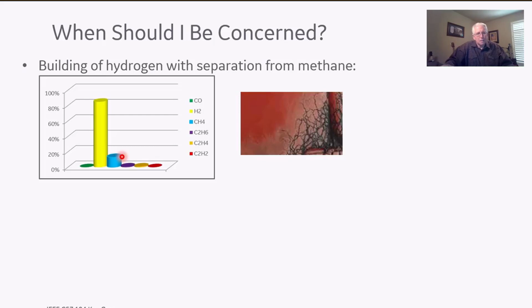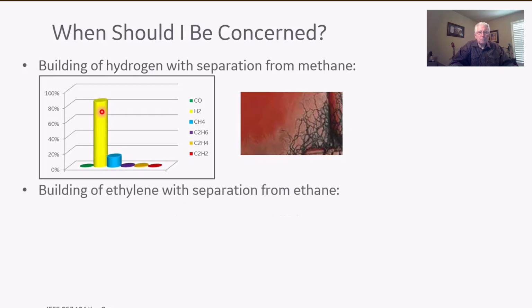the transformer or whatever. But bottom line is, if you begin to generate hydrogen in volume and you're capturing it, and you don't see a lot of movement out of these other gases, you can pretty much take it to the bank. You've got some PD going on in that transformer. So you just need a good separation of relationship here, because they both generate at 150 degrees C. So if you're capturing this much hydrogen in the transformer, it's a PD condition.